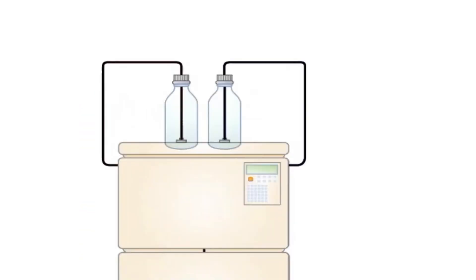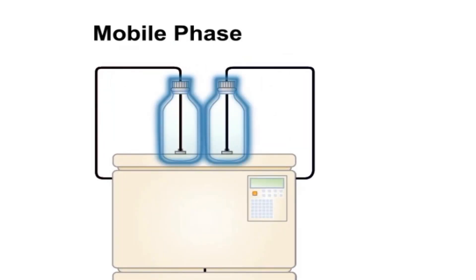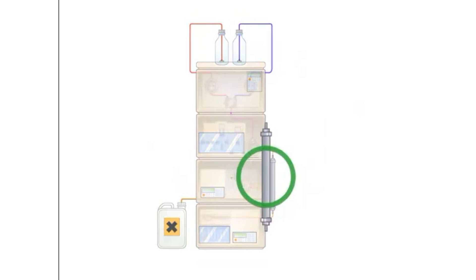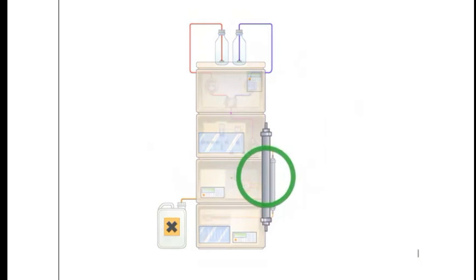The HPLC instrumentation consists of a series of simple components. First, the mobile phase, held in solvent reservoirs, is pumped through the system by one or more pumps at a constant flow rate. The sample is injected into the mobile phase stream by the sample injector.